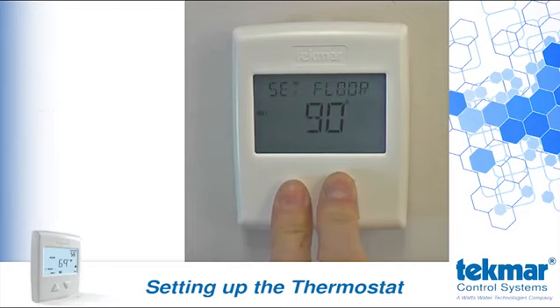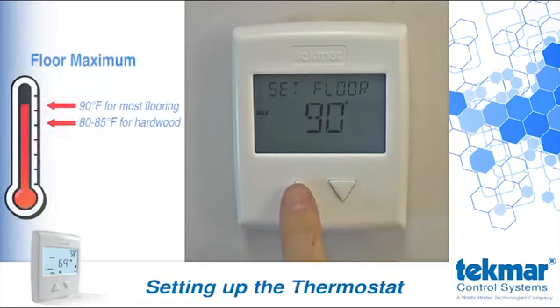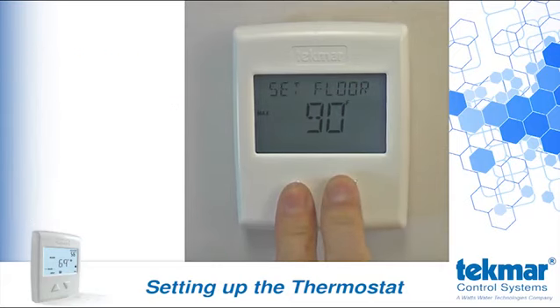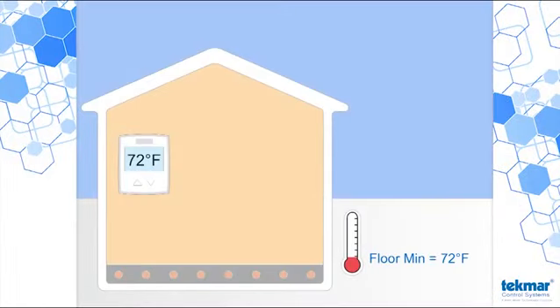If you're using an auxiliary floor sensor, the next setting will allow you to configure the floor maximum temperature. Refer to the installation and operation manual for this thermostat for some recommended settings based on flooring material. By configuring the floor minimum, maximum, and leaving the built-in room sensor on, the thermostat will operate the radiant floor between the minimum and maximum temperatures to achieve a target room temperature.